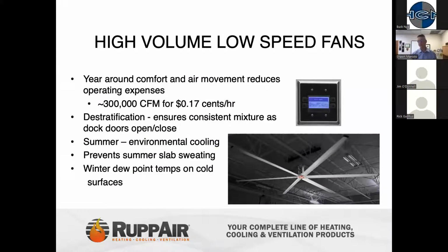Next, we get into the HVLS fans, what benefits they can provide to these applications. Very economical for moving a lot of air. Like I said, the air rotation, indirect air rotations were big in the past because they did that. They not only brought in heat, but they were able to turn over large amounts of air within the space. Now with the innovation of HVLS, they've kind of taken that place. Up to 300,000 CFM at 17 cents an hour is very, very economical.